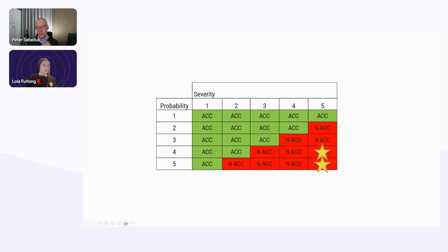We did reduce it as far as we could, but we couldn't go any further without adversely affecting the benefit risk ratio. Should this be acceptable? And probably not. Because from an ISO 14971 point of view, it would say that if it's unacceptable, you need to do a benefit risk analysis. And for the MDR, we are saying that you need to do that every time you have a risk. You should, because otherwise you couldn't determine when you stop reducing it.